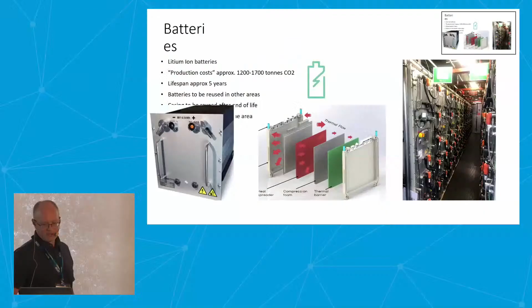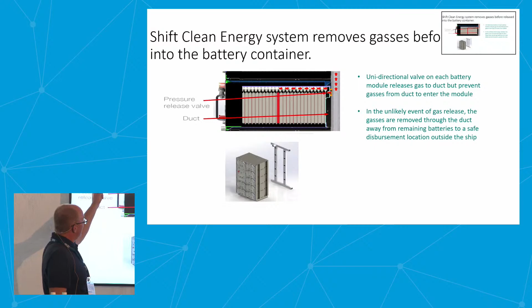And this is, we have Shift Clean Energy battery system. And this is how it's done. Each module has 24 cells. And in case you have a thermal runaway in a single cell, the flammable gases will expand through the release valve and out to this duct behind the racks.